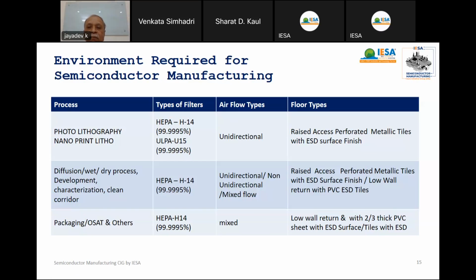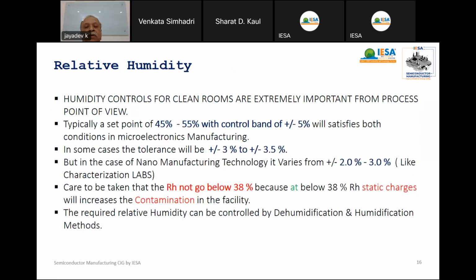So these are the normal construction materials required for the environment. More important is relative humidity. For semiconductor applications it is very important because it is the culprit. Typically, a set point of 45 to 50% with a control bandwidth of 5% satisfies both comfort conditions and the process requirement. In some cases the tolerance will be customized. But for nano manufacturing and characterization labs, it requires a stringent 2 to 3% around 45% humidity. One care you should take: if RH goes below 38%, static charges will increase, which increases contamination in the facility. So we should control this carefully. It should not go below 38% and should not go above 55%.